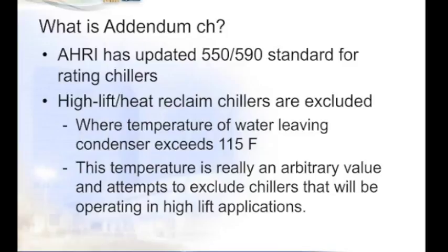These chillers are typically operating in very specific and very special conditions, which do not compare to testing at AHRI conditions. Sometimes these chillers may not even be able to operate at the AHRI conditions. I've had selections that I've asked manufacturers to do for me, and when I ask for standard AHRI conditions, they say, nope, we can't get the output. So that's a very real issue, and I'm glad that ASHRAE has decided to exclude those from this updated standard.